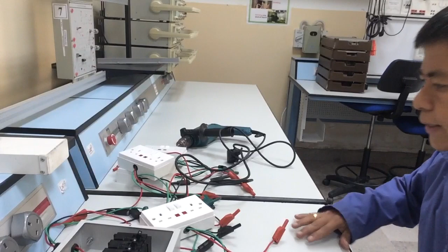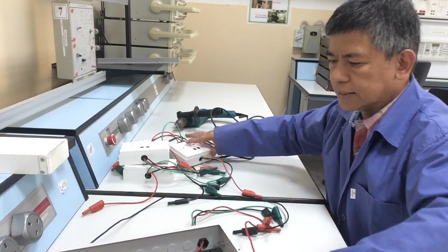Let's connect the ring circuit. From the distribution board, we connect to SSO number 1: line to line, earth to earth (green to green), and neutral, which is the black color here.